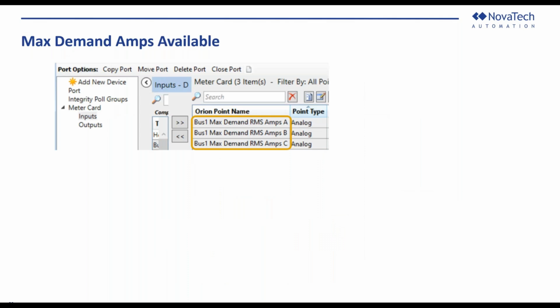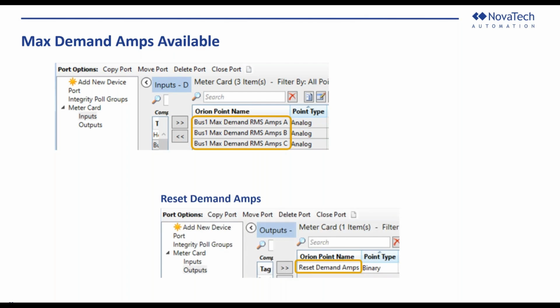We mentioned demand amps. These are values that you can read from the meter card. Fairly simple. Again, you can set the demand interval as long as you want. And there is a reset on your demand amps as well.